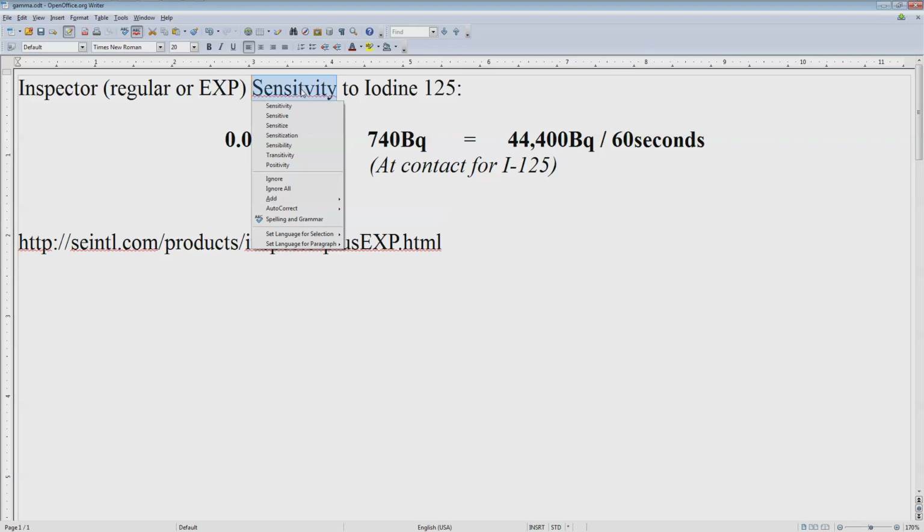Here's a misspelled word. That is now spelled correctly. According to them, they give their sensitivity for their detector with iodine 125, which I think is absolutely ludicrous. It's because it is an effective pure gamma emitter. It actually emits X-rays and gamma rays through electron capture, which is kind of funny, but it acts like a pure gamma emitter.